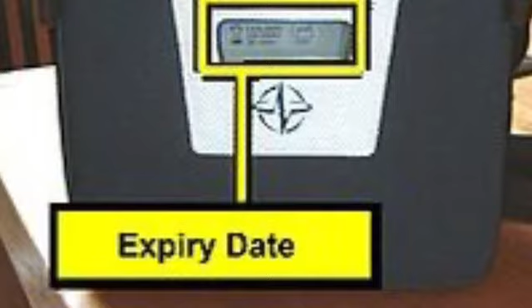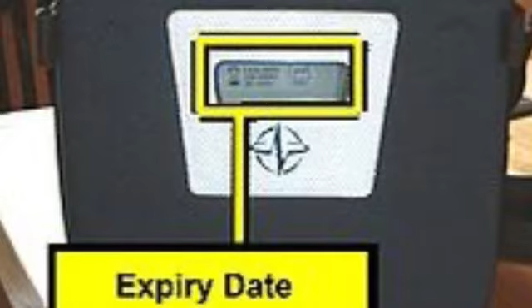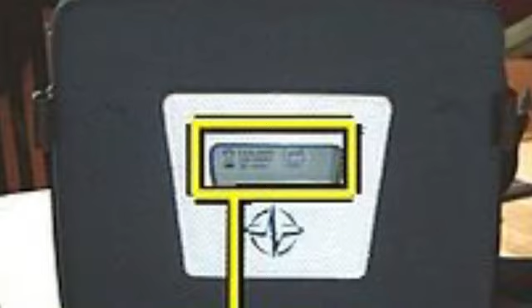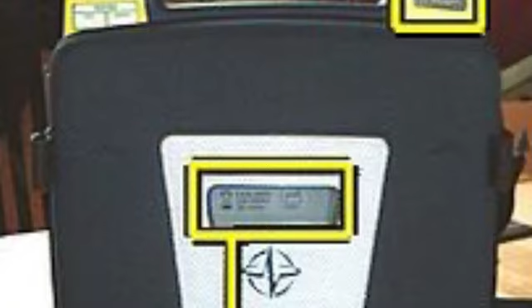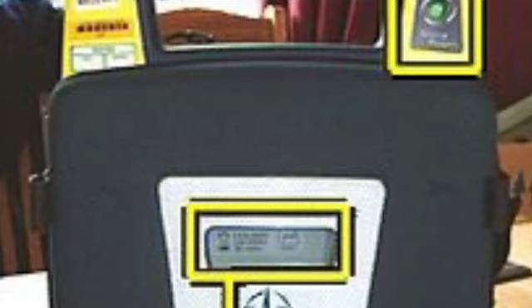Sometimes they throw error codes, especially if they get super cold. So if you ever go by an AED and it has a red light flashing or is beeping, making a noise, that most likely means it needs service. So we would want to turn that on. It would tell us what service it requires, whether it's, again, battery replacement, pad replacement, or just service in general. The AED does a self-check every night.